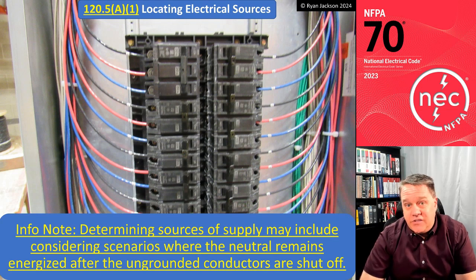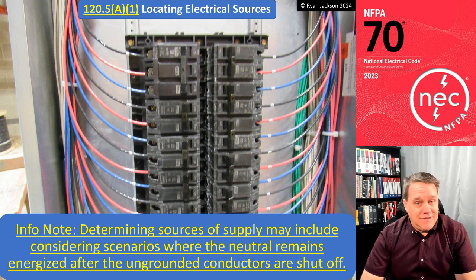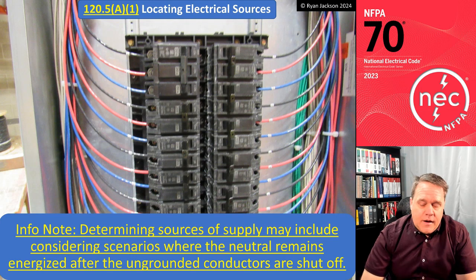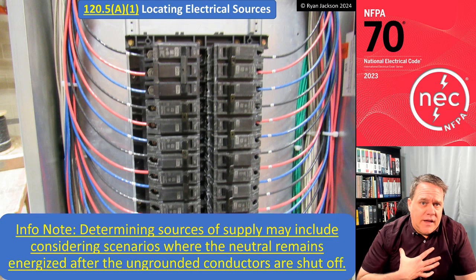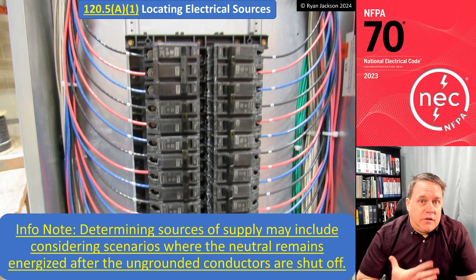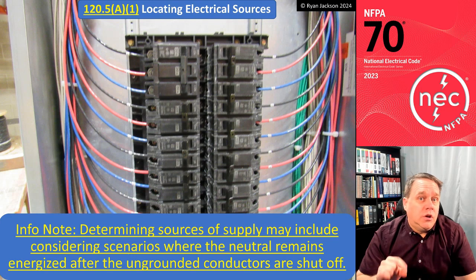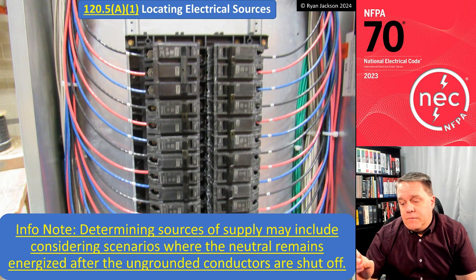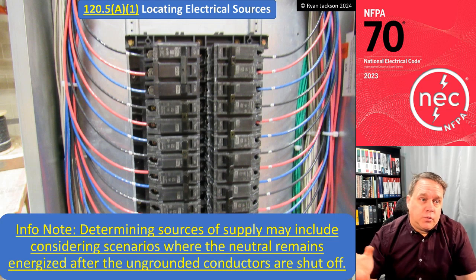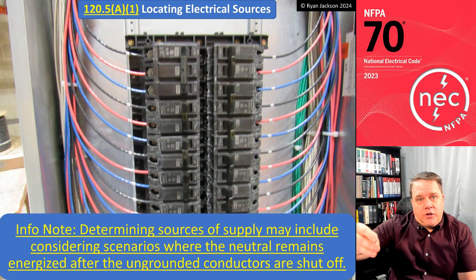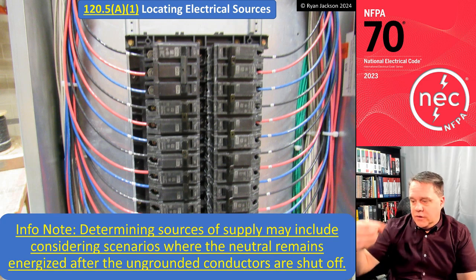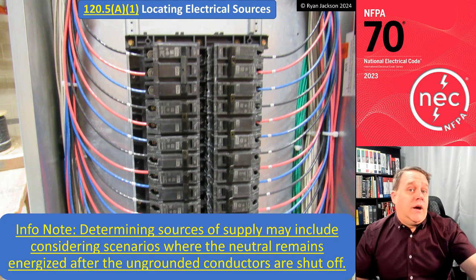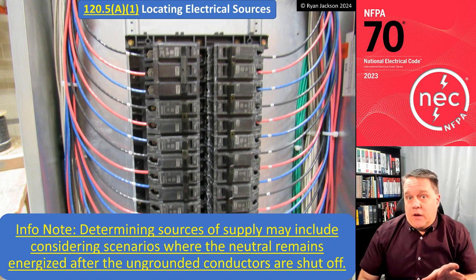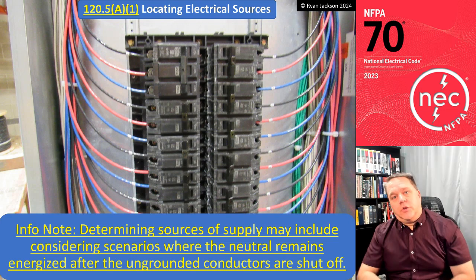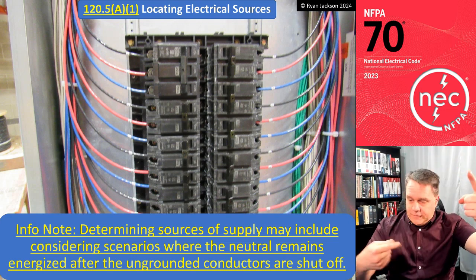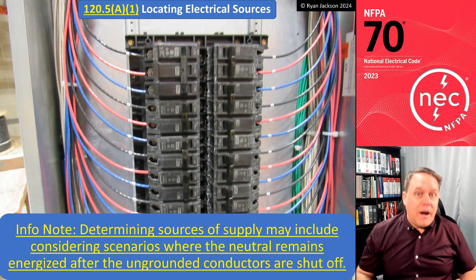All right, so that's been in the NEC since 2008, but I've got news for you. Not every building was built after 2008. I was an electrician long before 2008, and I did commercial work, and I can tell you that every time I could share a neutral, I did share a neutral. And yeah, if it was new construction in a perfect world, then I would put the 3 phases next to each other, circuits 1, 3, and 5, or 6, 8, and 10, or whatever. But boy, I'll tell you right now, if I was in an existing panel board where you've got openings scattered throughout, sometimes circuits 1, 41, and 16 might share a neutral.